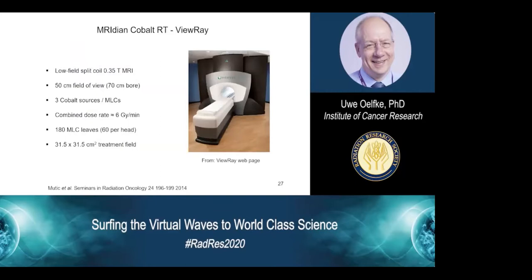The technical parameters of the system are like this. It is a low field split coil magnet of 0.35 Tesla. The field of view is 50 centimeters in a 70 centimeter bore, as indicated before. 3 cobalt sources and MLCs, which yield a combined dose rate of 6 gray per minute. And the MLC has 60 leaves per head, and the treatment field is almost 32 centimeters squared.